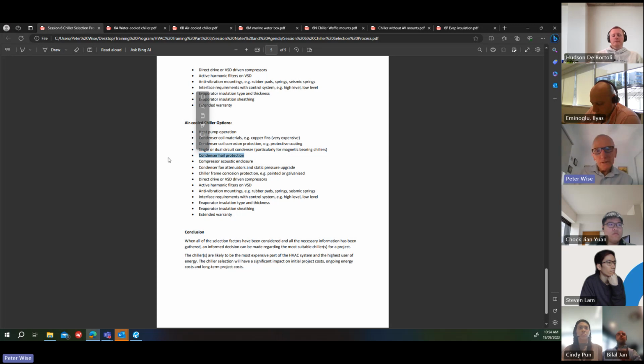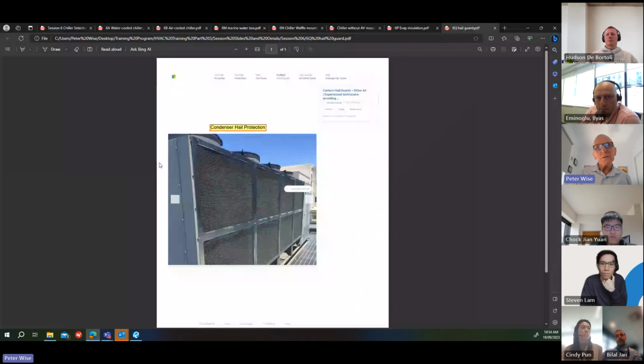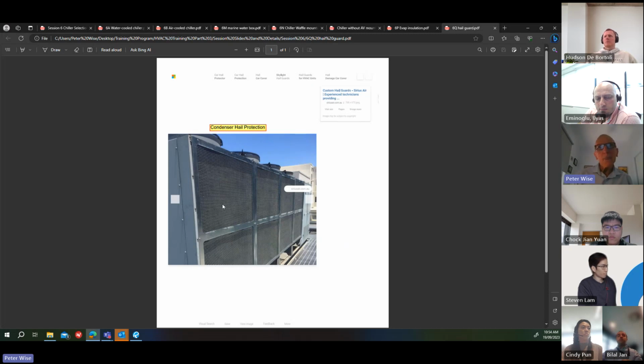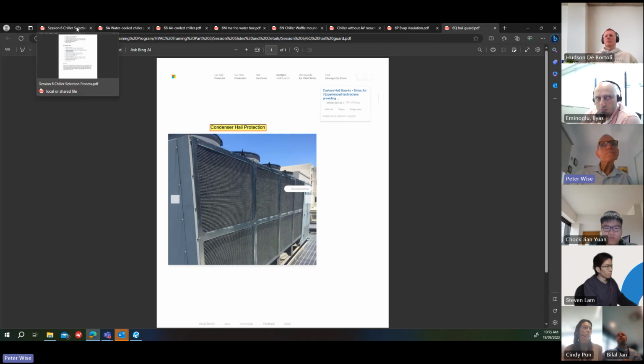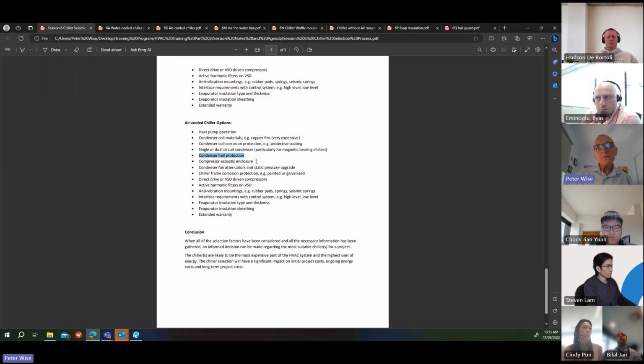Now, the air-cooled chillers are outside, and if it's in an area that may be prone to hail, hail can do a lot of damage, right? So you can get hail protection on the condensers. So that's a picture there. It's a protective guard over the coil, so that the hail hits the guard, might do some damage to the guard, but doesn't affect the heat exchanger, the condenser on the chiller. So that's something to keep in mind that might be needed, particularly in places like some parts of Queensland. They get hailstorms with very large hail, and they can do a lot of damage.